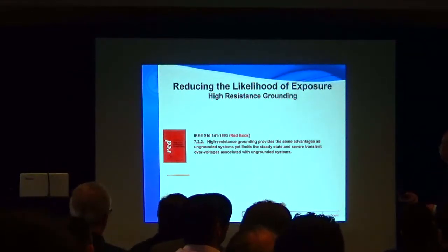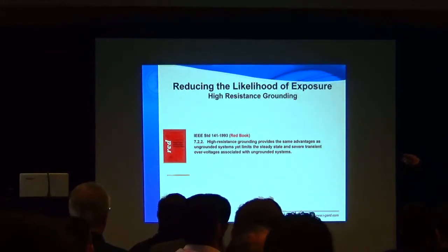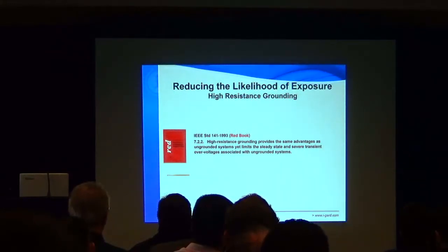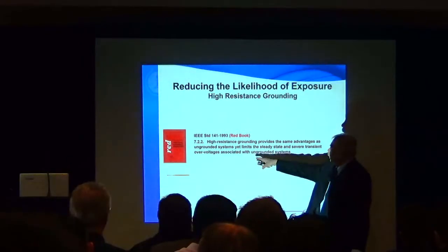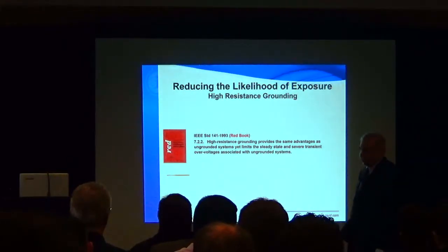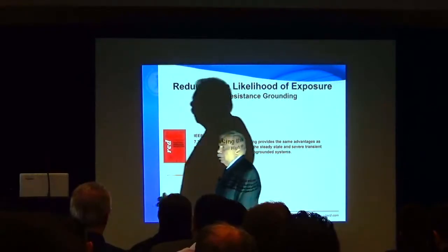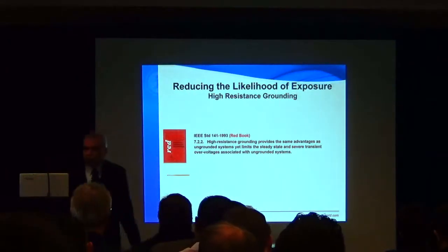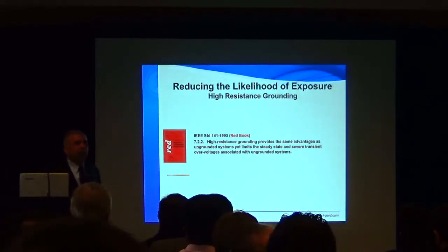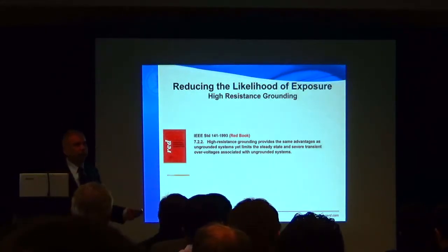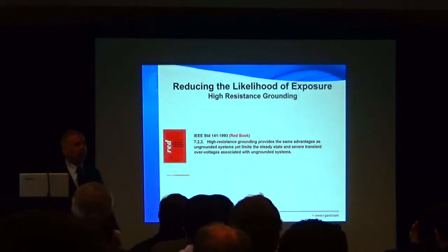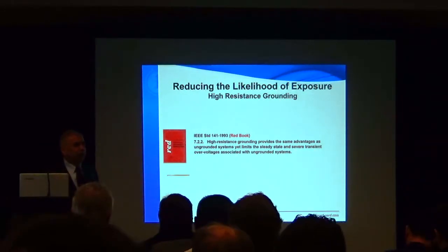So this Red Book says high resistance grounding provides the same advantage as ungrounded systems, yet limits the steady state and severe transient overvoltage associated with ungrounded systems. Clear, absolutely clear indication that we should not be using ungrounded systems anymore. If you have any legacy ungrounded systems, most of them have been converted. If you haven't converted them, it's a good time to convert, because you are getting into some further insulation problems going forward.